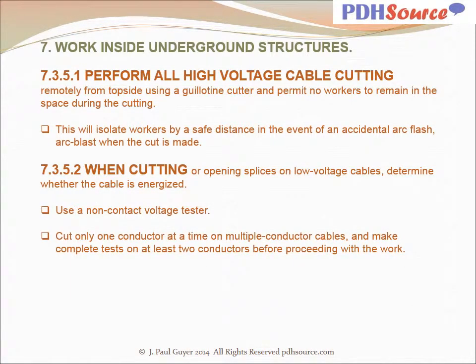Perform all high voltage cable cutting remotely from topside using a guillotine cutter and permit no workers to remain in the space during the cutting. This will isolate workers by a safe distance in the event of an accidental arc blast when the cut is made. When cutting or opening splices on low voltage cables, determine whether the cable is energized. Use a non-contact voltage tester. Cut only one conductor at a time on multiple conductor cables and make complete tests on at least 2 conductors before proceeding with work.